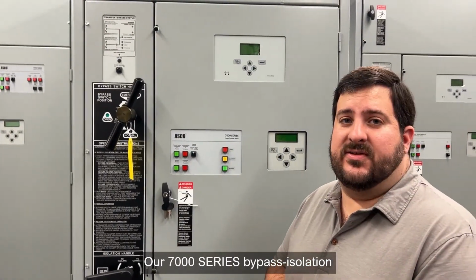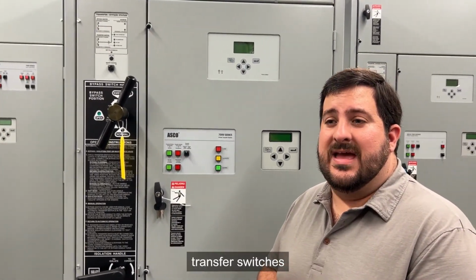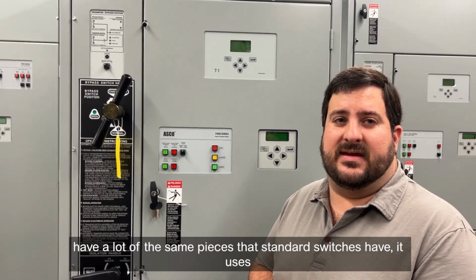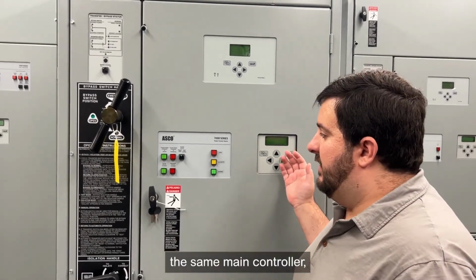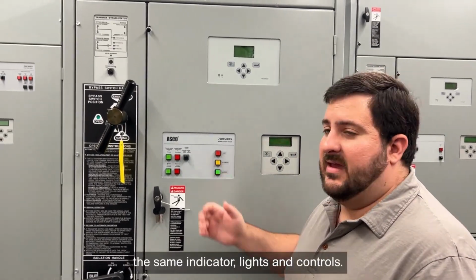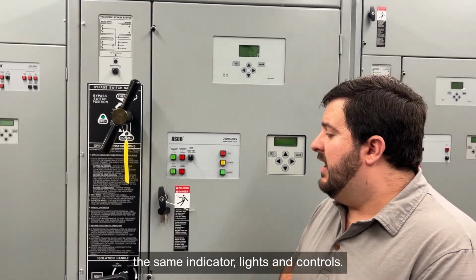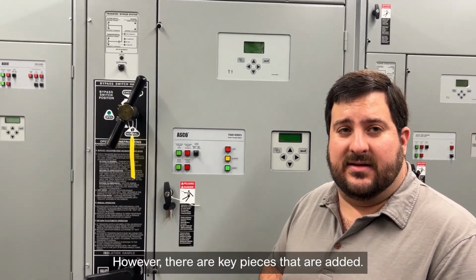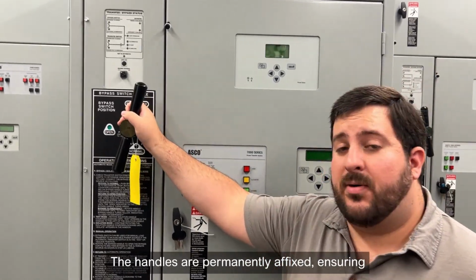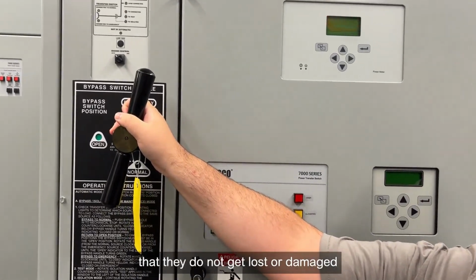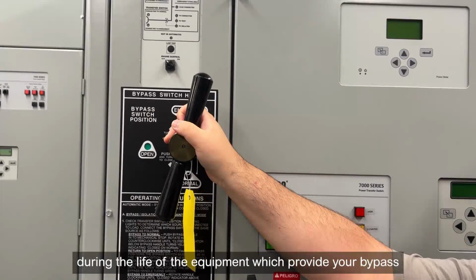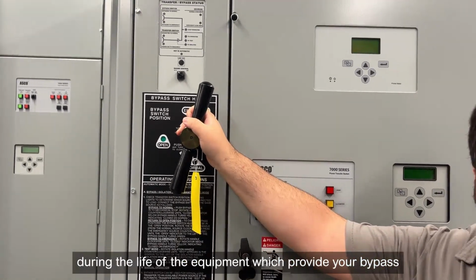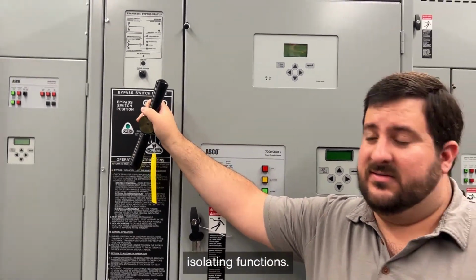Our 7000 series bypass isolation transfer switches have a lot of the same pieces that a standard switch has. It uses the same main controller, the same indicator lights and controls. However, there are key pieces that are added. The handles are permanently affixed, ensuring that they do not get lost or damaged during the life of the equipment, which provide your bypass and isolating functions.